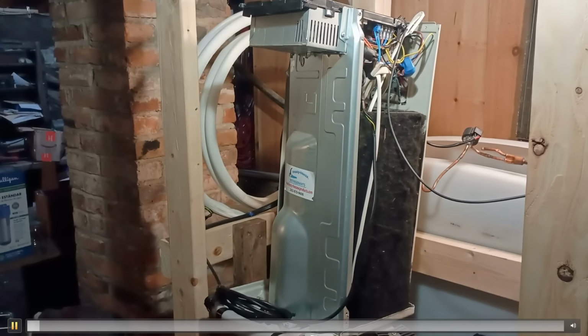And then there's bulkhead fittings that I installed on various sides of this thing as well. Really important, so there's a heater coil on the base of the unit. This is so if ice starts forming on an outdoor unit, it wants to melt that ice. It's got some temperature sensors that are actually on the front of the evaporator, and at certain times it's going to turn on this heater.